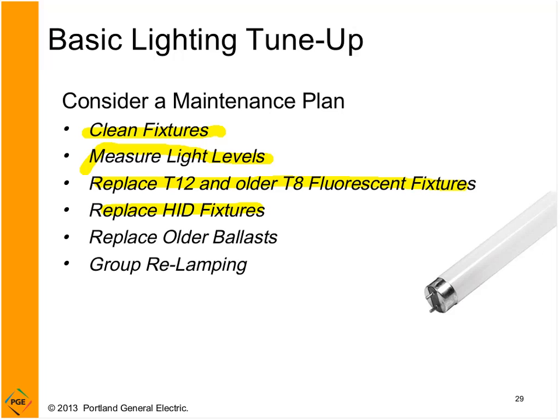But those types of fixtures, you can improve your performance if you replace them with either T8s or T5 fluorescent fixtures. And even LED fixtures are coming on the market that are cost-effective and good replacements. Then replace older ballasts. Like I said, the T12s are typically going to have a magnetic ballast, and newer ballasts are electronic and help you reduce your energy consumption. The ballast is the voltage controller for the lamp.